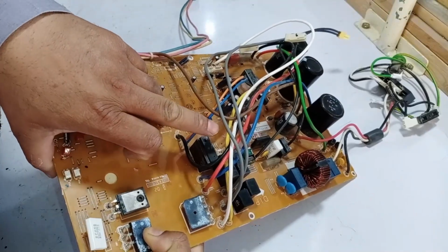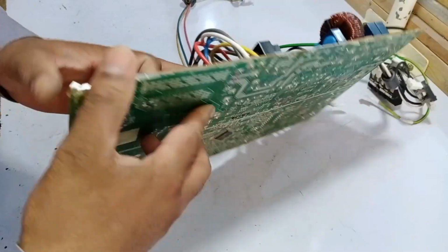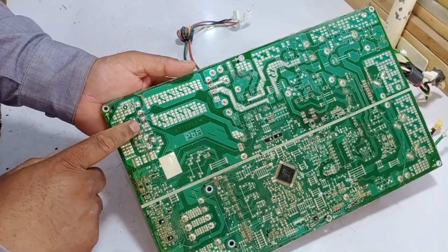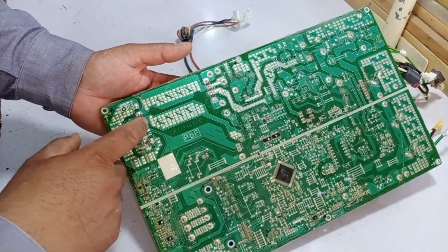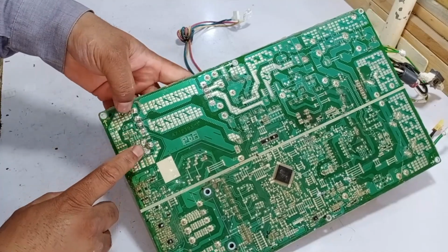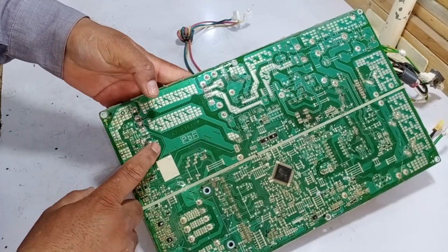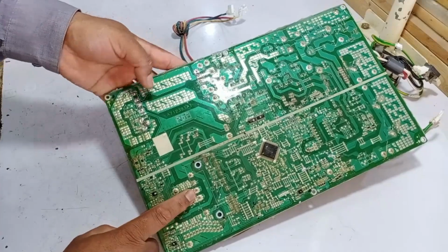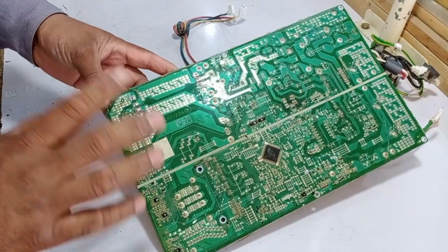When this relay turns on, it completes the rectifier's system circuit. As the circuit completes, the voltage increases and is directed to the IPM, enabling the system to operate. Once the circuit is fully functional, the compressor and other components turn on, and the system begins to work efficiently.